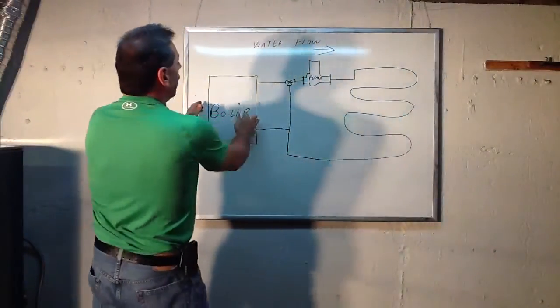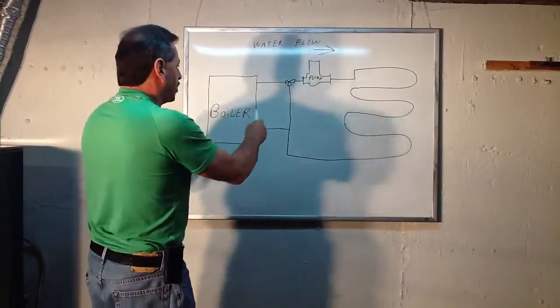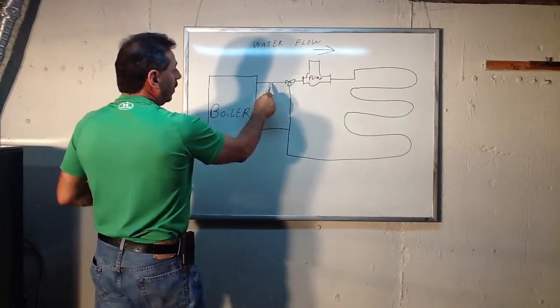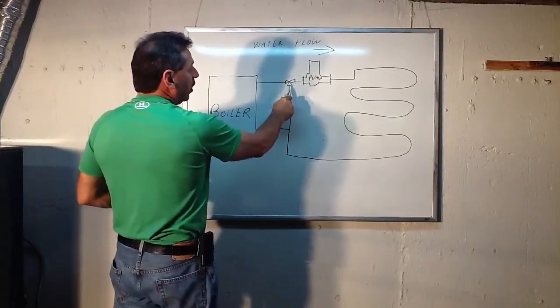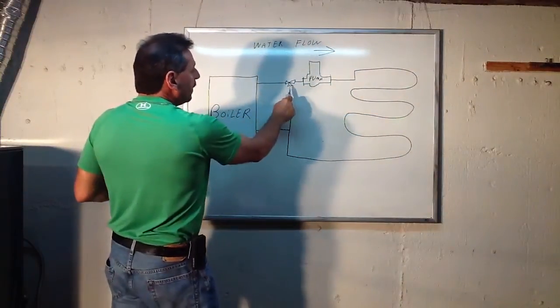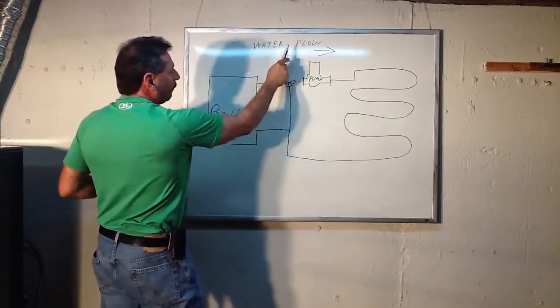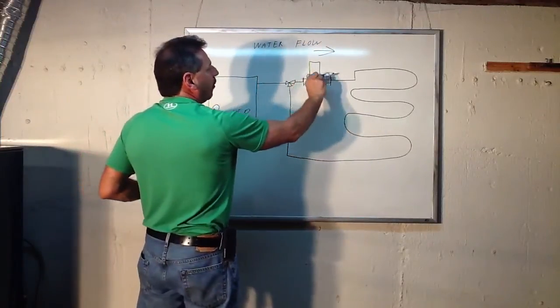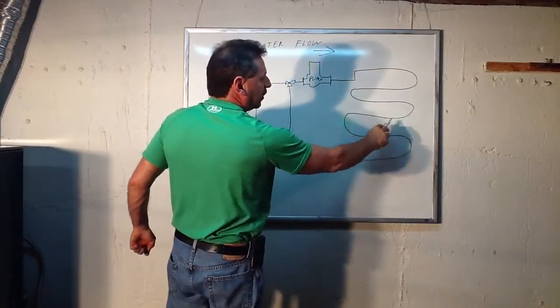The boiler is set up and running at 180 degrees. You immediately come out of the top of your boiler. The first thing you install is a mixing valve. Right after the mixing valve is going to be your circulator pump. Remember the water flow is away from the boiler going into the radiant tubing under the floor.